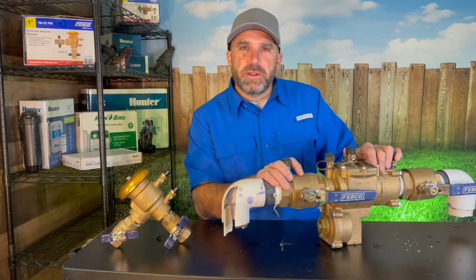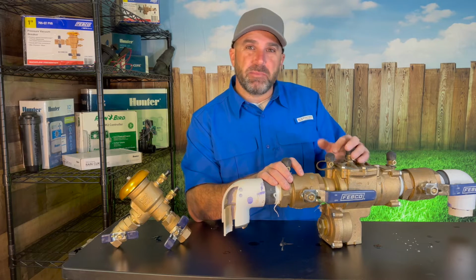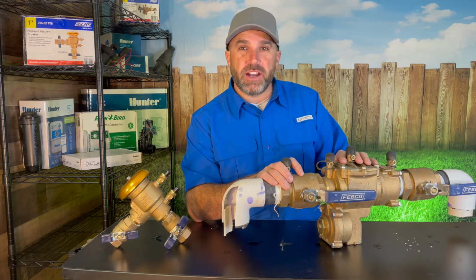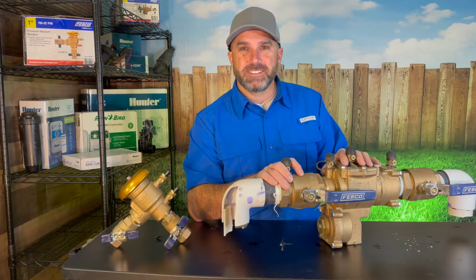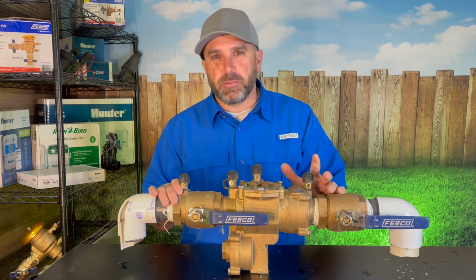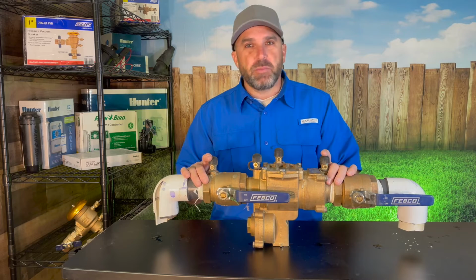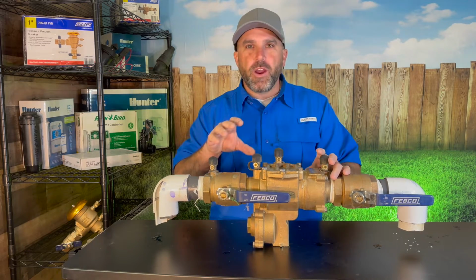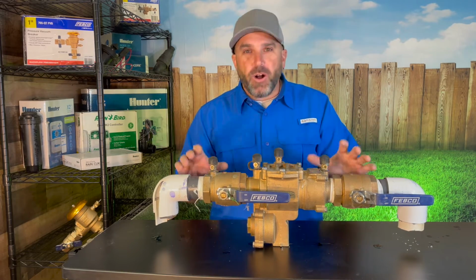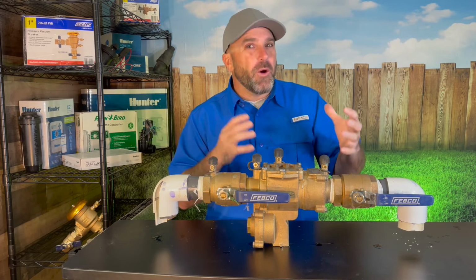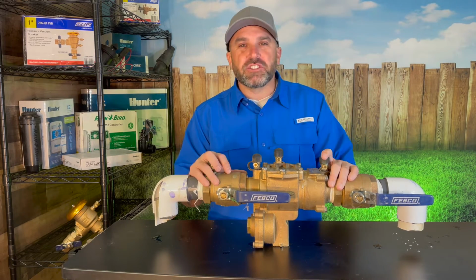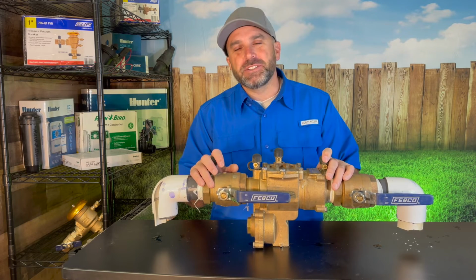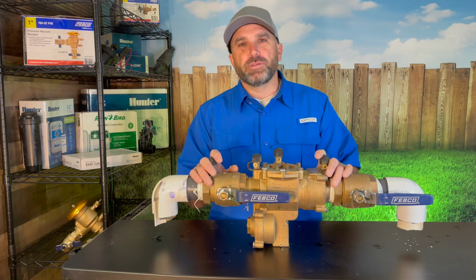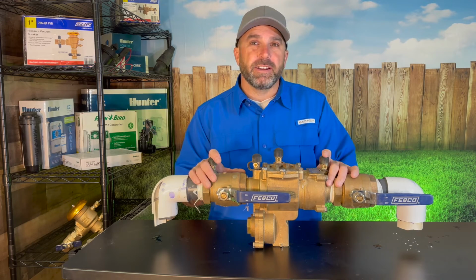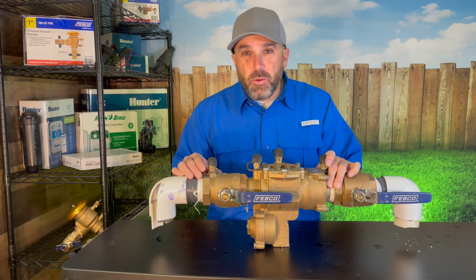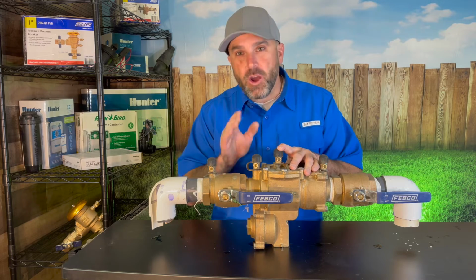I'm going to show you on this RPZ and use it as an example of what happens to a backflow device when it is not winterized. We had this 2-inch RPZ installed on a project, and it was not covered up with anything. It just came up out of the ground and was fully exposed to all the elements. I had it in mind to go out there and cover this thing up with something and didn't get to it in time before we had a bad cold front come through and freeze and break this backflow device. So let me show you what happens to a backflow device when it is not winterized.